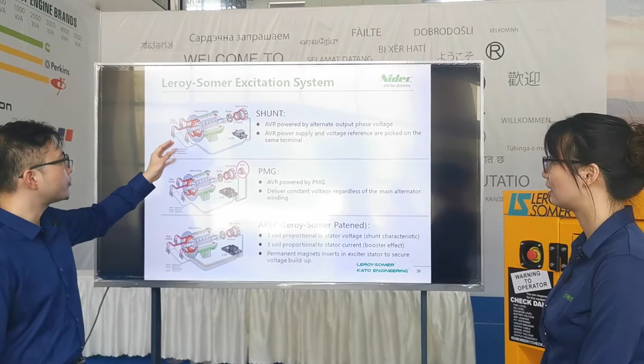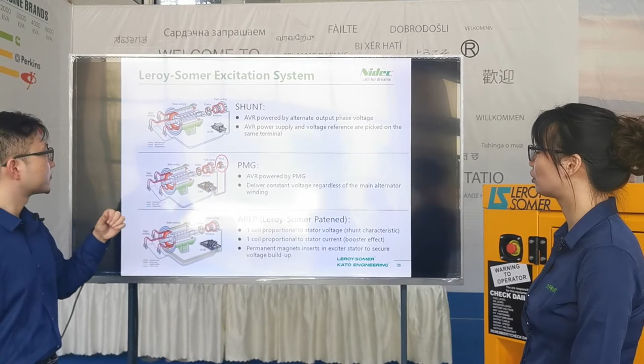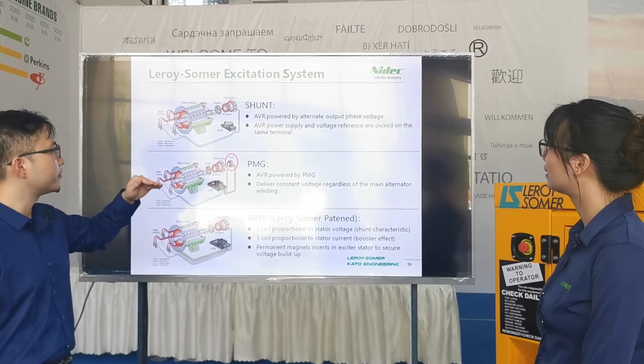For shunt, the AVR is powered by the alternator output phase voltage, meaning from the terminal. So it will have the same voltage and same stage as the alternator. For example, if the alternator gets a distortion load, the same will impact the AVR. So if the generator gets a short circuit, this AVR will be broken, and when shunt meets a short circuit, the whole alternator will stop.